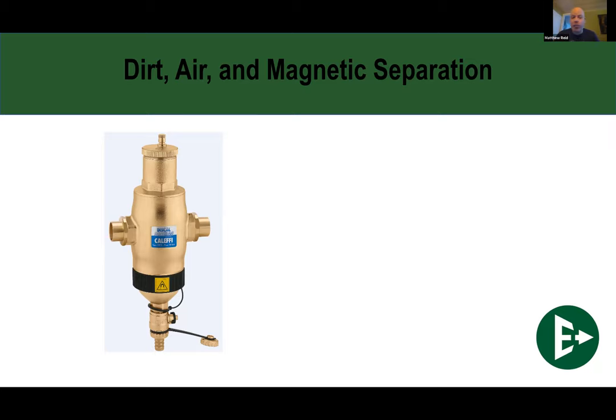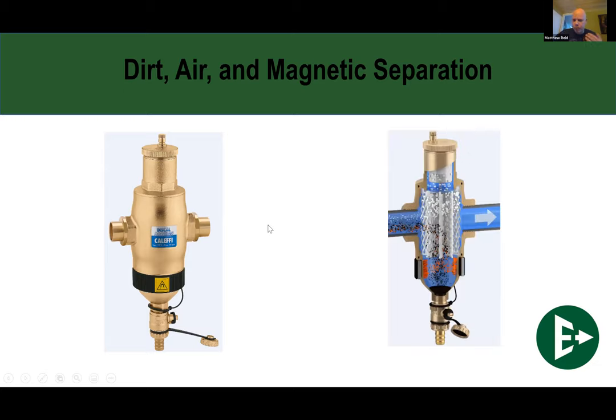They're still extremely effective. I do like to see two pieces rather than one piece, but there are different pieces that we can use as well. Here's a little cutaway of what it looks like on the inside, with the air hitting that medium, like shaking a water bottle: air comes out of solution, rises to the top and pops out. The dirt and ferrous metals fall to the bottom by gravity, and the ferrous metal sticks to the band. Take the band off to do your flush, and away you go.